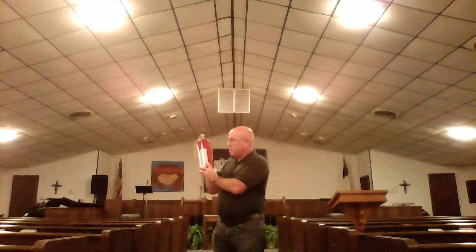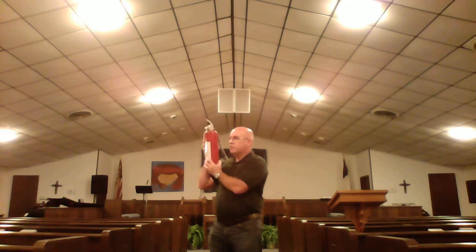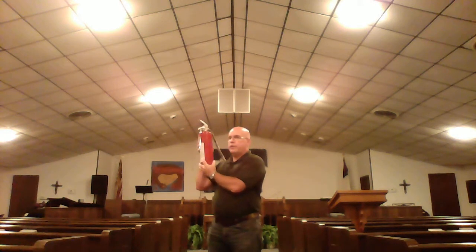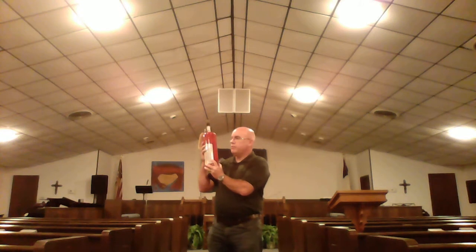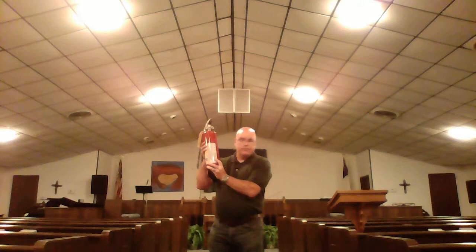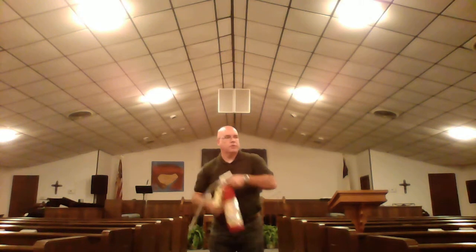And if you ever want to know, there's a date usually stamped on these right here. Like this one says 1993. This is one of the ones that we pulled out of service here at the church. And I just got it out. So that's the reason why we replaced them, is because they were well over 10 years of age.